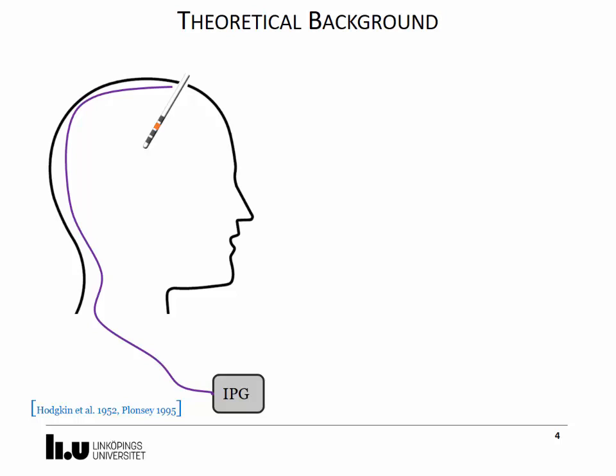Electric current flows through the subcutaneous extension and lead wires to the active electrode, shown in orange. The current then crosses the electrode tissue interface and flows back to the case of the IPG, which is acting as the anode.